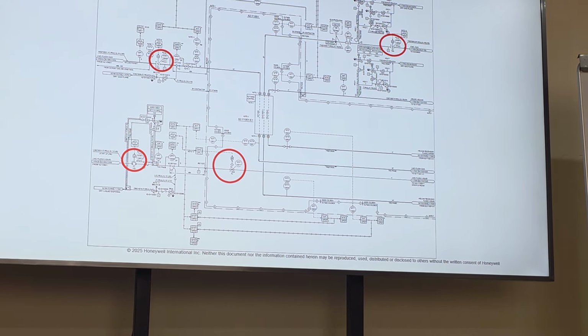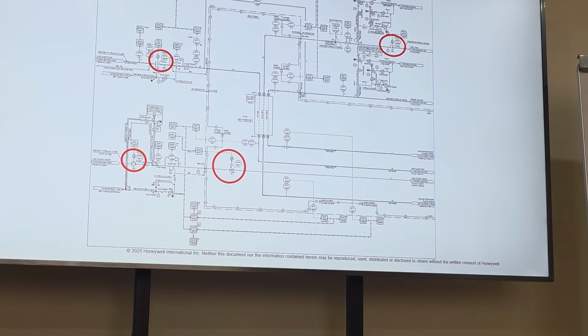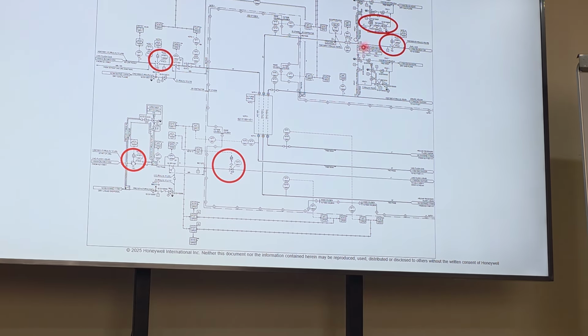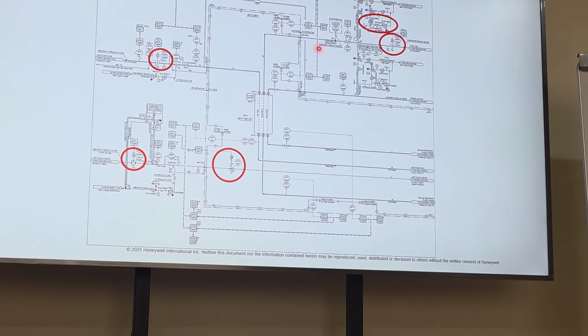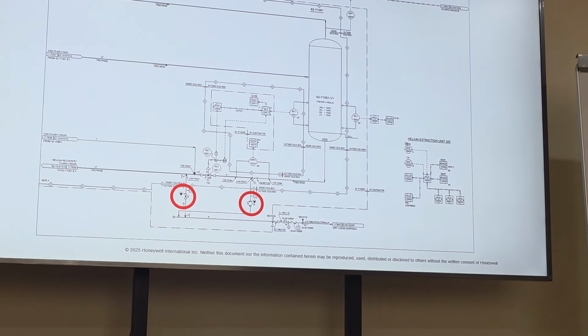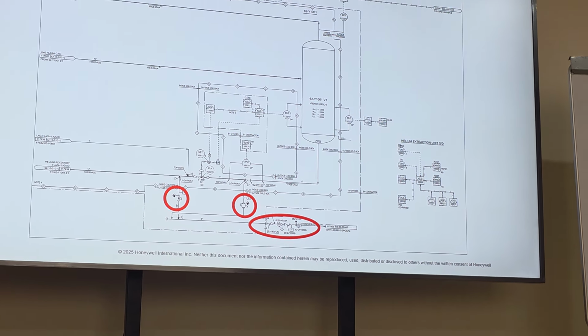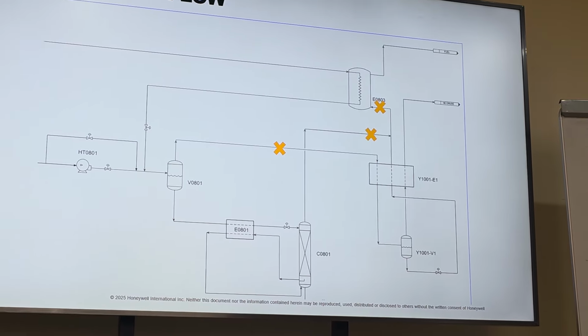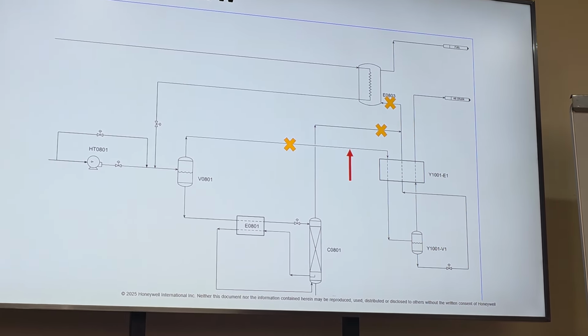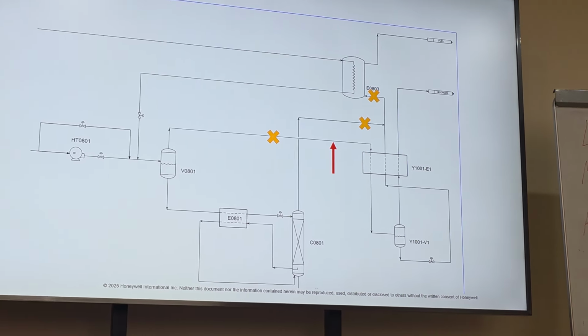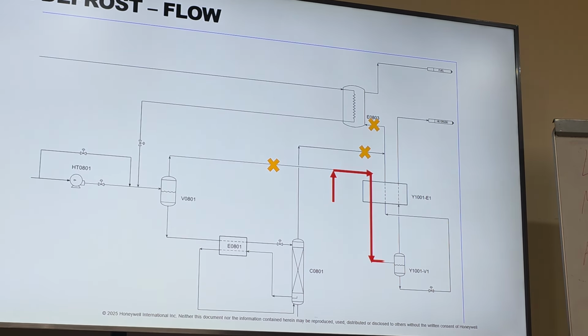And you can open up the ESDs to serve as a vent, right? So we can open these up to serve as vents on the discharge side to help pull and purge and defrost. So in this case, right, we're doing a warm defrost, so we're not trying to cool down yet, we're just trying to dry out the equipment. Right, so we're going to inject defrost gas, normal flow path.